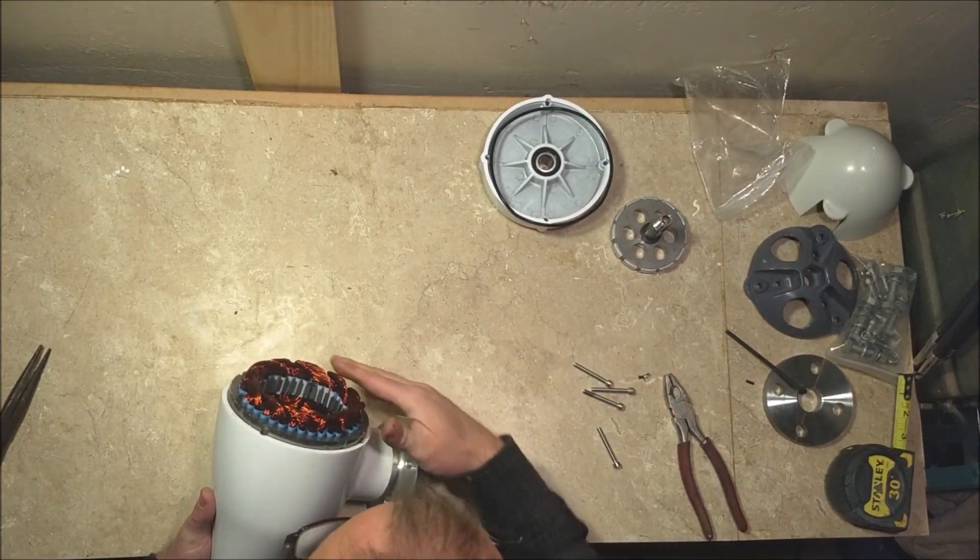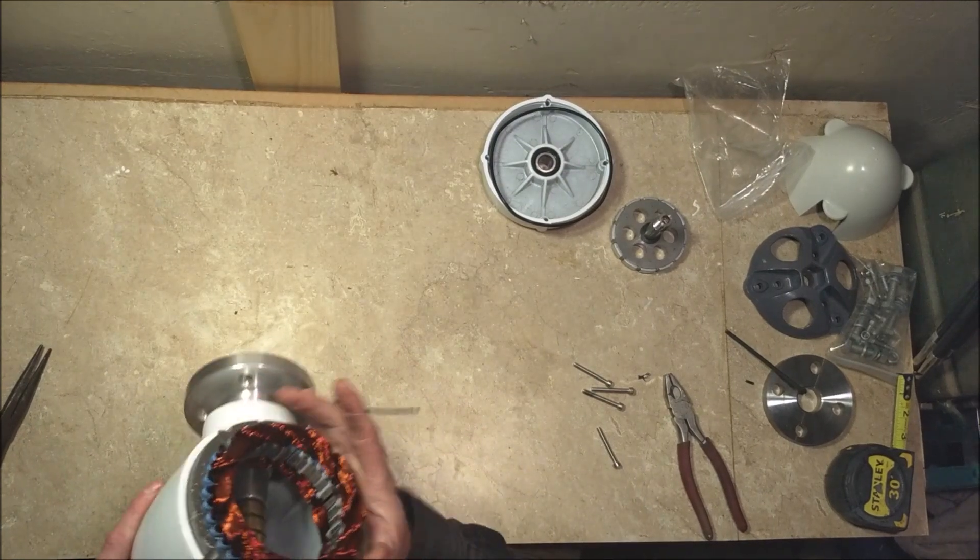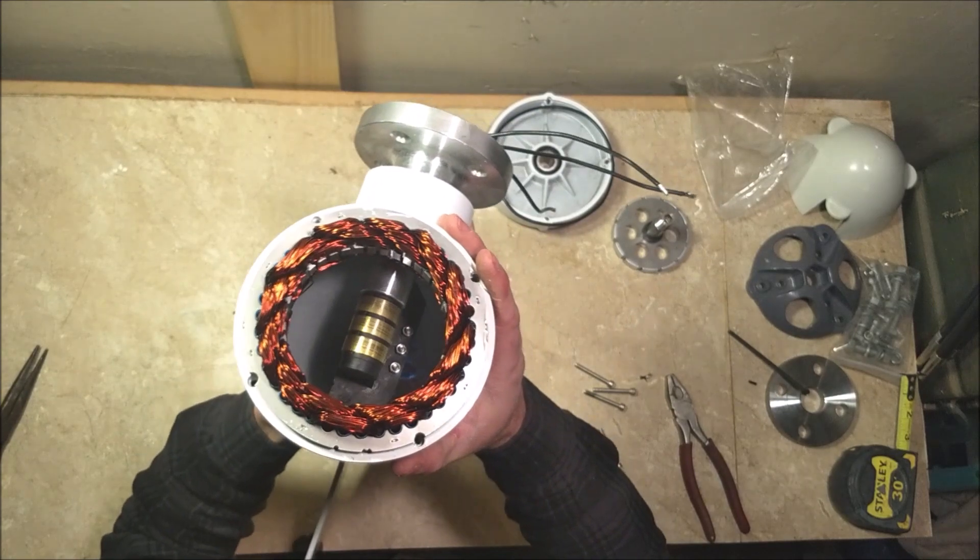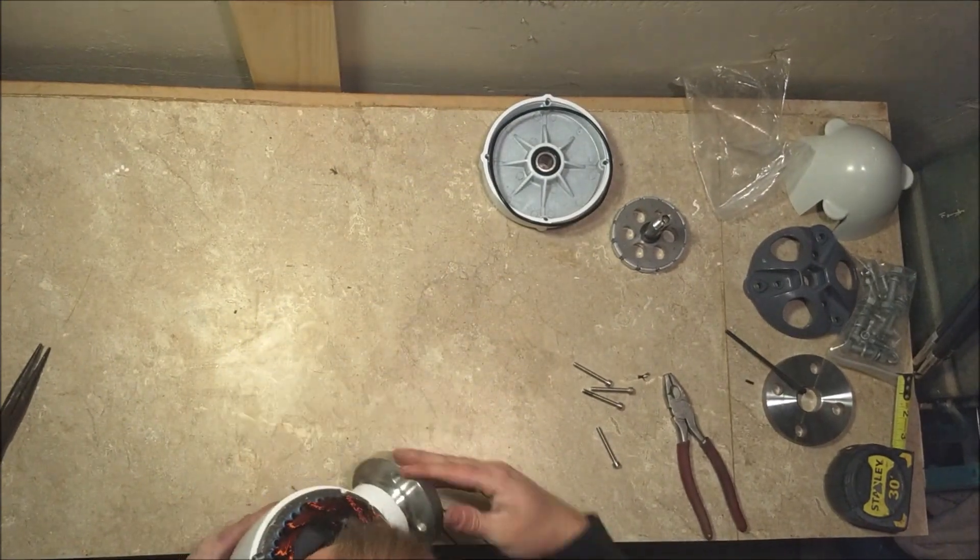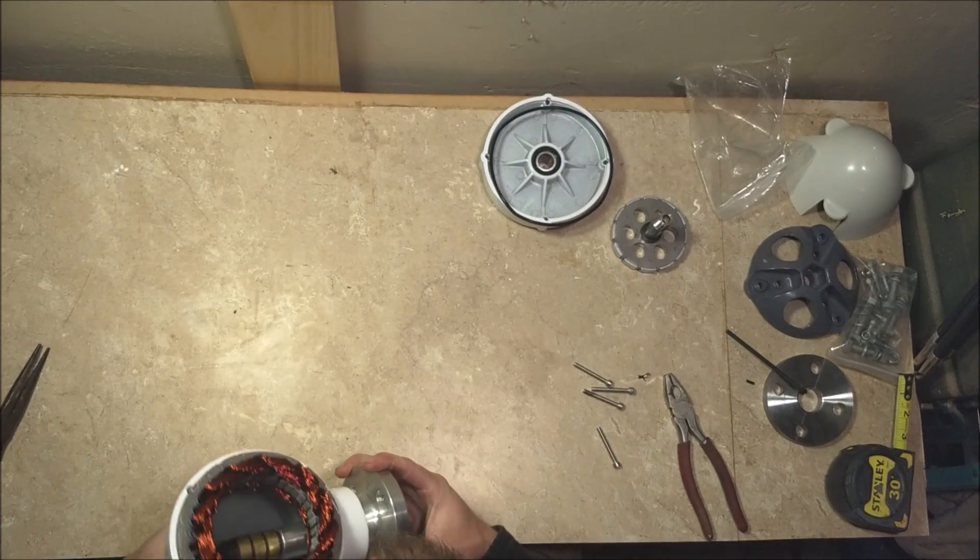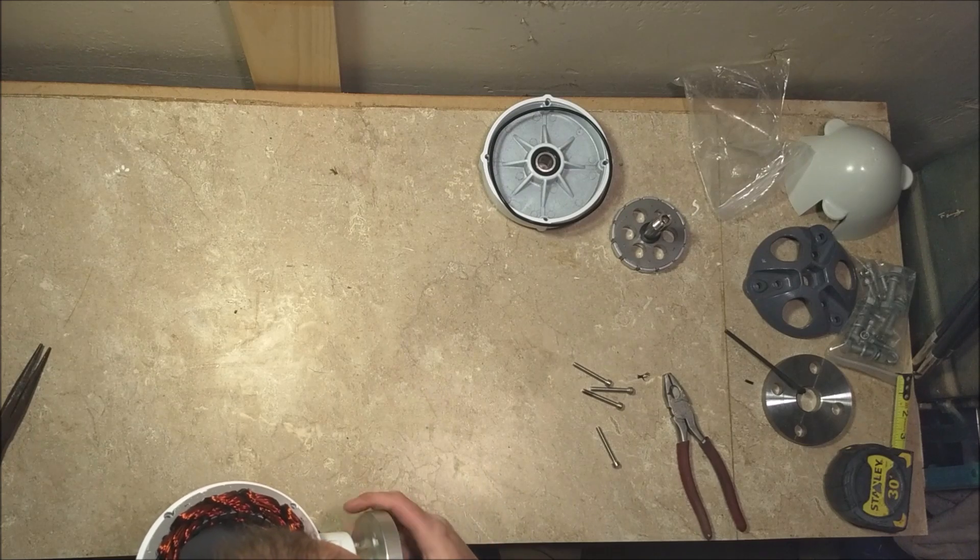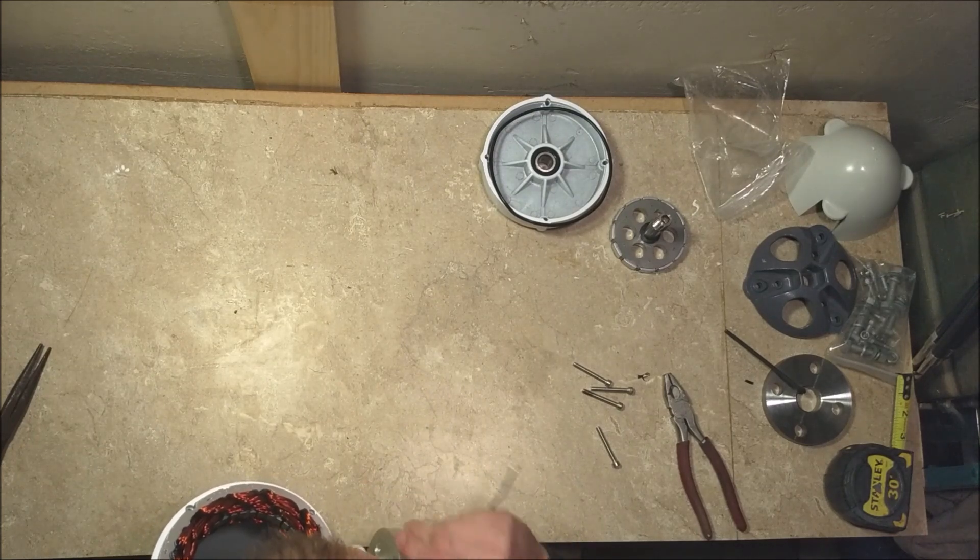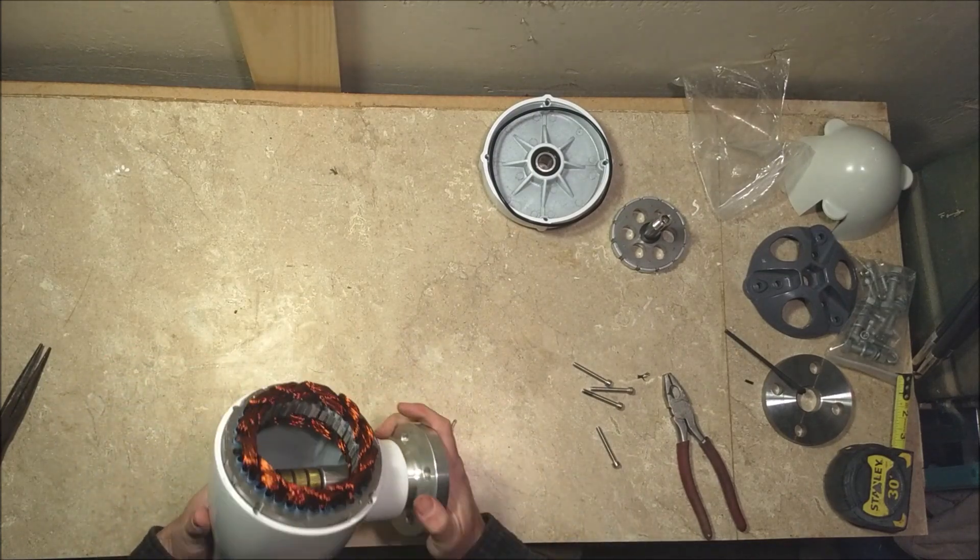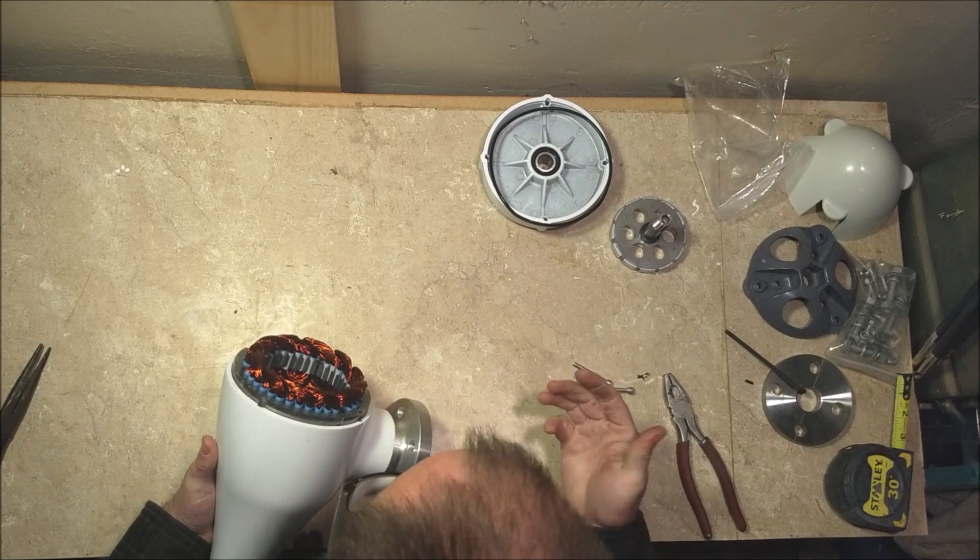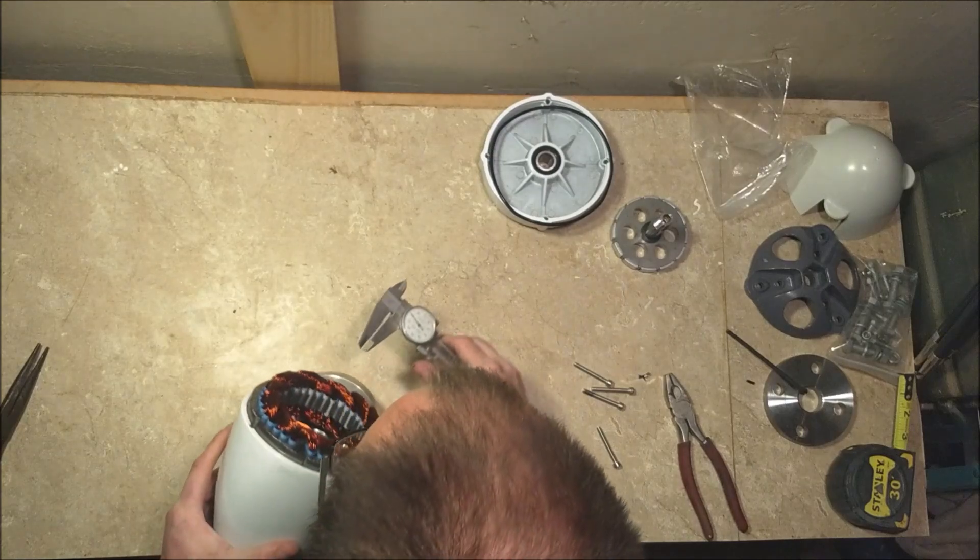Now the Chinese stators, they're never coated, there's no lacquer or anything over it. None of them ever are. You see a slip ring straight in the back. Slip ring is very generic, it is just a steel tower with brass rings up at the top. And that's how it conducts its electricity, it's all brushed. Let's measure, get a couple of spots on the wire.